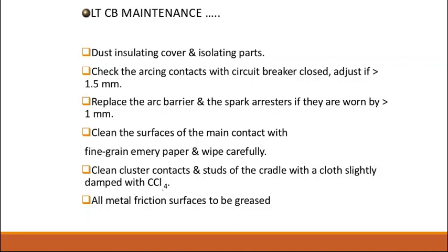Also there is an I square R loss. So if there is an I square R loss, the heat produced by the breaker will be more, so arcing effect will come into the picture. So when we use emery paper and wipe, the carbon deposit will be removed.